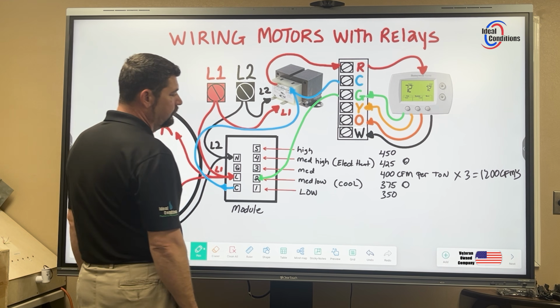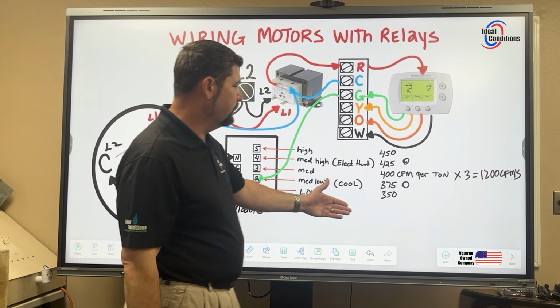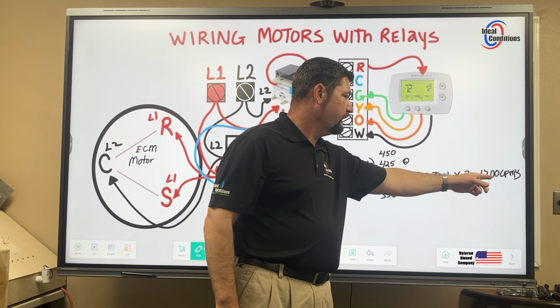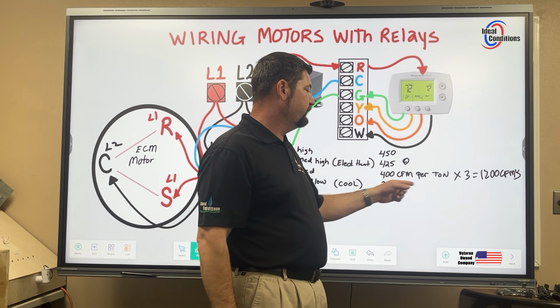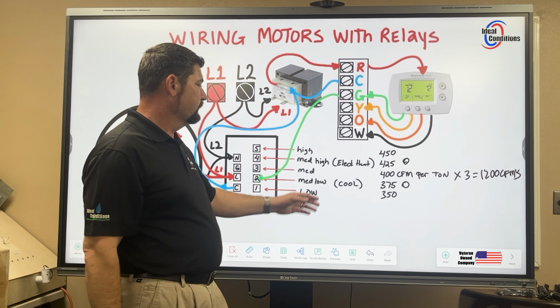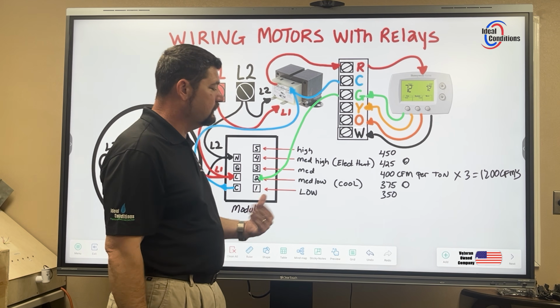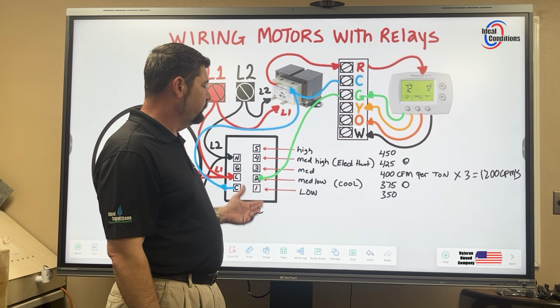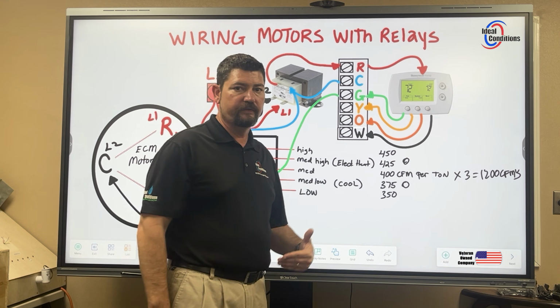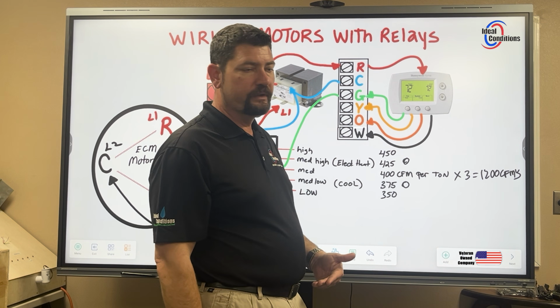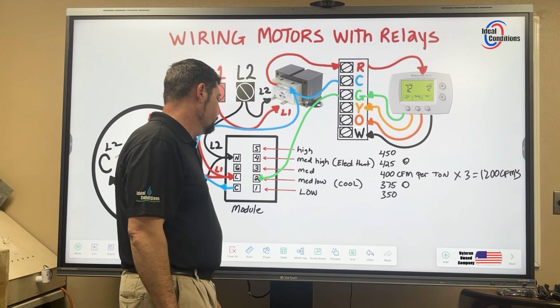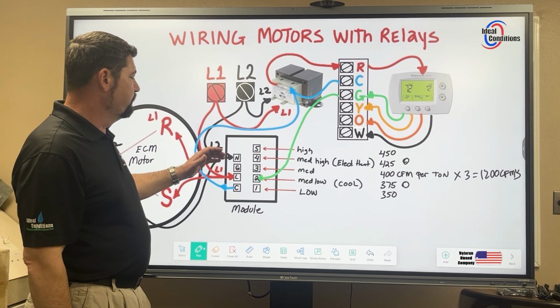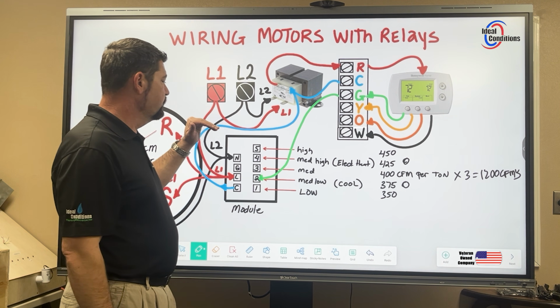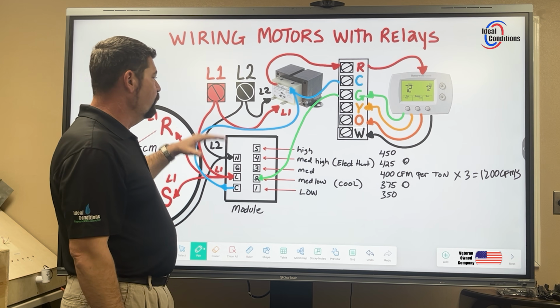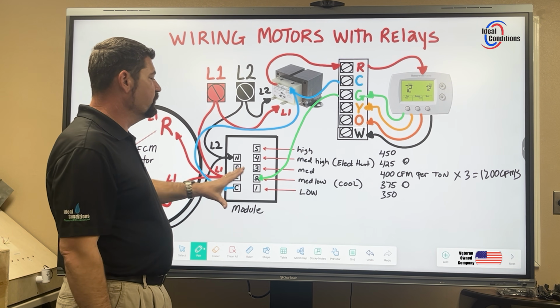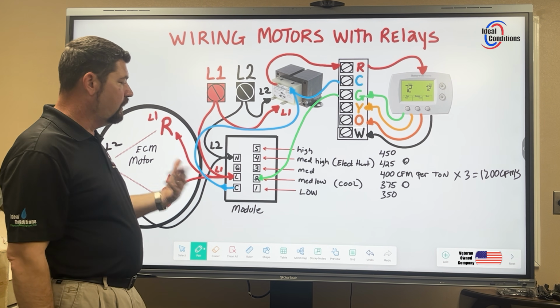375 CFMs. I'm losing, if this was a 3-ton, I would be 75 CFMs less, so I would be at 1125 CFMs. So 1125 CFMs, it's not a lot of CFMs, but it's enough to make sure that we transfer enough heat, get a good, decent superheat, get a lot of comfort going for your home. But it's not enough speed to run medium-low with a heating element in conjunction with that. So that will cause some issues.